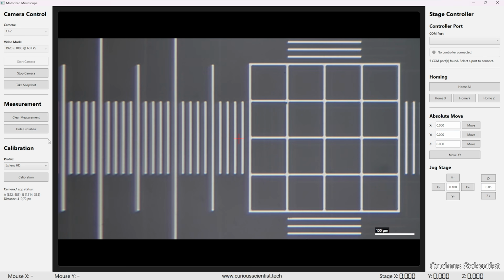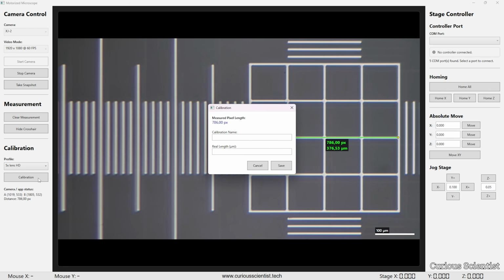To further complicate things, the calibration must be performed for each objective lens of the microscope, since they have different magnifications and fields of view. A pixel-to-pixel distance will be rendered as a different distance in micrometer units. To perform a calibration, we need a calibration slide with known distances, and we need to draw a line along a known length. Once the line is drawn, the user can click on the calibration button and can name the calibration, typically with the name or the magnification of the lens.